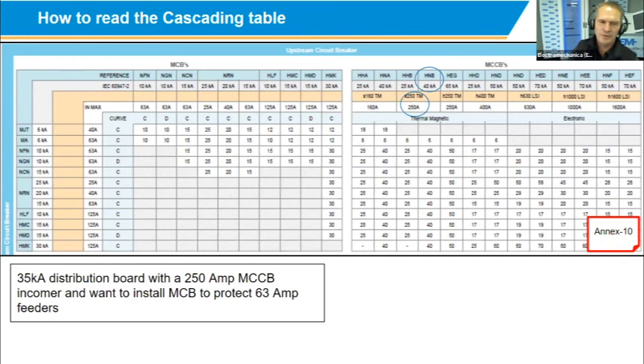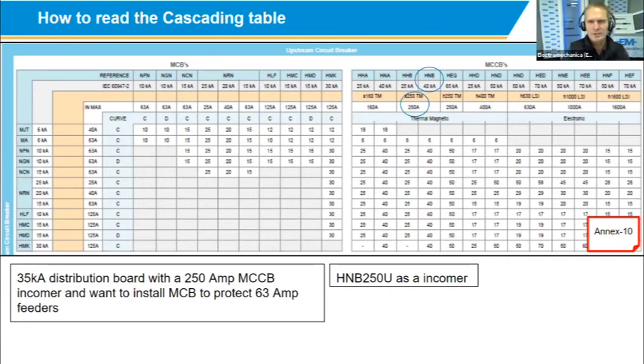So for a 35 kA short circuit, you are allowed to go higher. So if you don't find a 35 kA circuit breaker, you can go to 40 kA. It will still open at a certain time. The only difference is that the 40 kA circuit breaker can handle a 40,000 amp short circuit. So no problem in going bigger. So we now found that the X250 range with the TM, thermal magnetic tripping technology in it, will be suitable for my application. So now I've got the circuit breaker that I want to use.